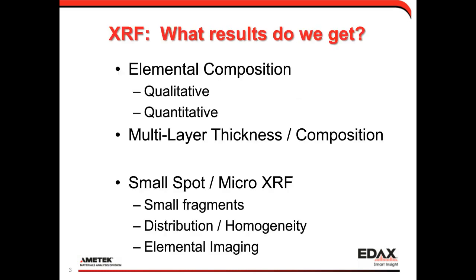X-ray fluorescence gives us elemental composition, both in a qualitative and quantitative sense, and we can do multi-layer thickness and composition with XRF as well. Small-spot micro-spot XRF lets you analyze small fragments by concentrating excitation down onto them. You can analyze more than one fragment at a time, put several fragments onto your sample handling stage, and automate acquisition. You can also look at large pieces, do distribution analysis to determine homogeneity, and do elemental imaging to get a picture of elemental distribution.